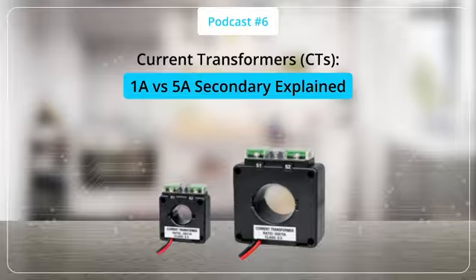Moving ahead, let's understand CT accuracy class and how it relates to secondary current. Accuracy class defines how precise a current transformer is. For example, a class like 0.5 is used for metering and allows a small margin of error, while classes like 5P are used in protection systems where detecting faults is the priority.